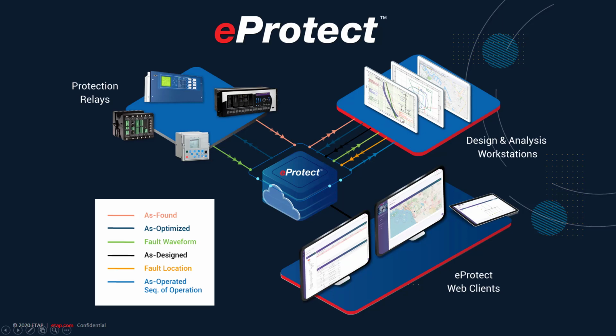You can communicate with the workstation and design analysis system. So the ETAP analysis software can connect to the eProtect remotely, again having the right access levels and communication settings. And we'll get the information from the eProtect downloaded to ETAP. You'll be able to do your analysis of all the protection and evaluation of the protection schemes. And then the system will provide you with a light interface. It's a web-based interface that allows you to view and monitor all the different settings of the device.